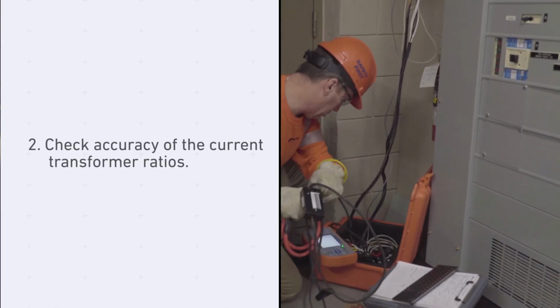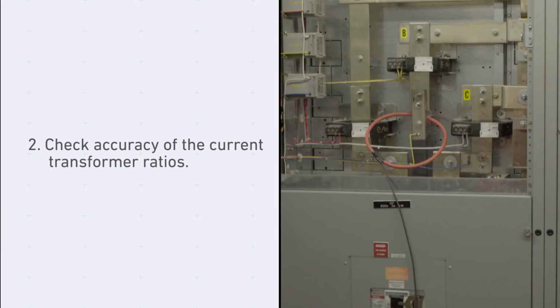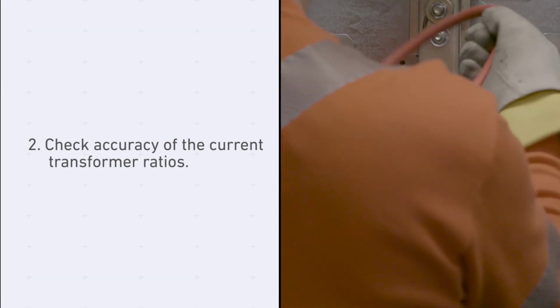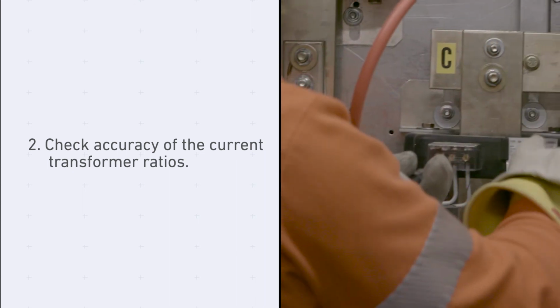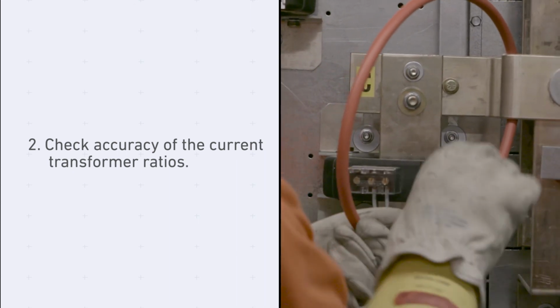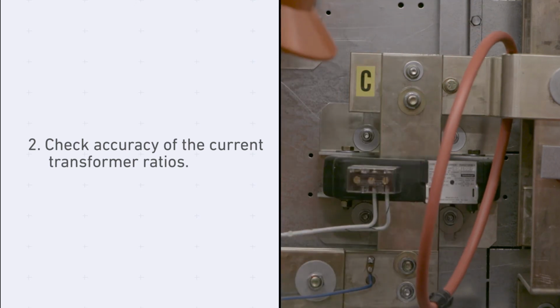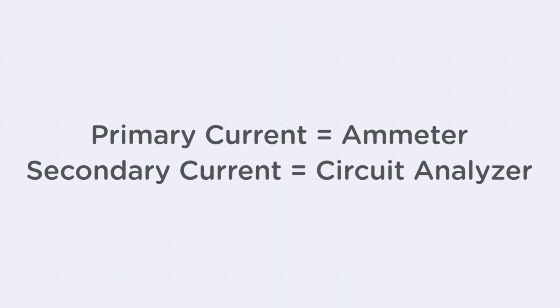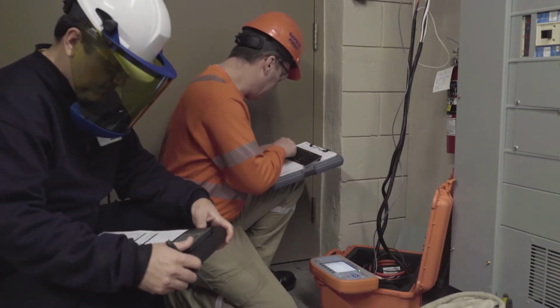Using a suitable ammeter that is capable and set to measure current in the expected range, check the accuracy of the current transformer ratios. This is usually accomplished by reading both primary and secondary current simultaneously. Primary current is obtained via the ammeter. Secondary current is obtained via a circuit analyzer. Record the results on a worksheet.